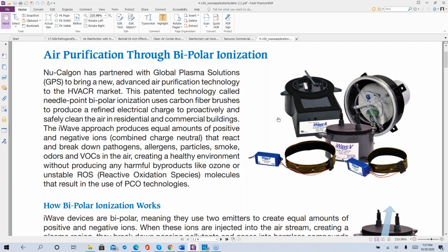So we recommend that you install them, and these will last a lot longer. I've heard that they will go 5 to 7 years before you have to replace the carbon fiber brushes, which are relatively easy to do and relatively inexpensive. But why make them pour these millions of ions into dead air? So by having an interlock, what we're typically doing when we're doing the installation, and we're already in the high dozens of these, and we will soon break into the hundreds. They are selling like hotcakes.